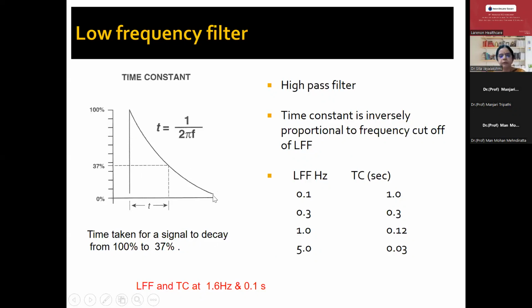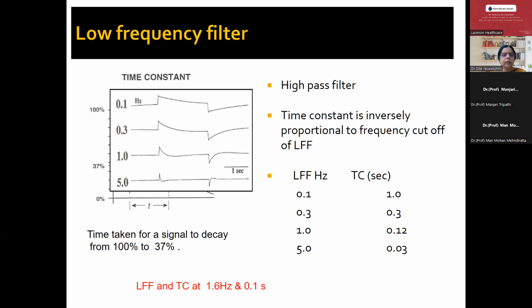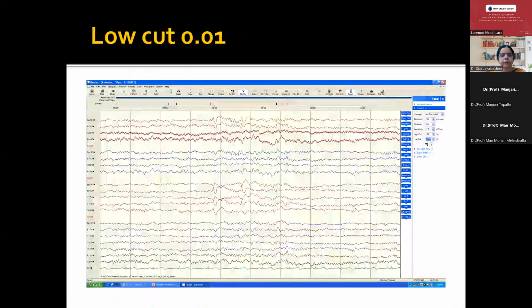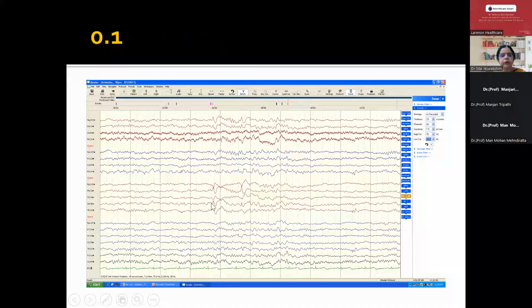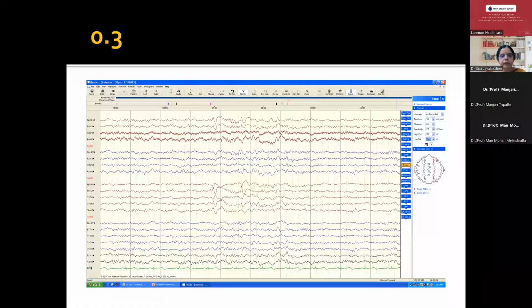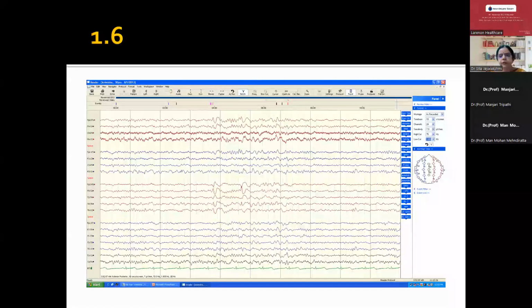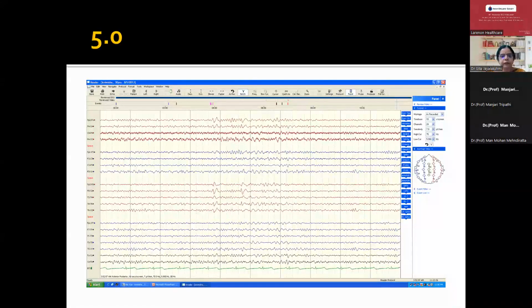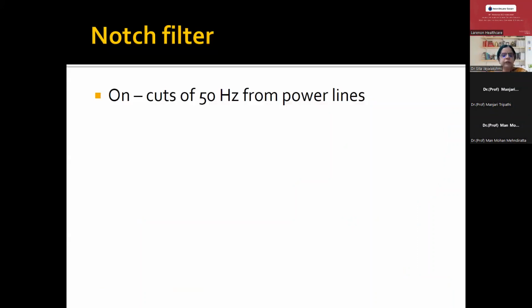That is 37%. So normally, if you keep the time constant, this is how you see the wave of the EEG. But when you make it at 5, you see this, the morphology totally changes, and this is called over damping or under damping. So this is about the low cut filter of 0.01. Keep looking at the artifact as well as the spike morphology. And again at 0.1, 0.3, 0.5, 1.6, which is normally kept, and again at the 5. So both high frequency and low frequency filters, one should be careful when you are keeping them.